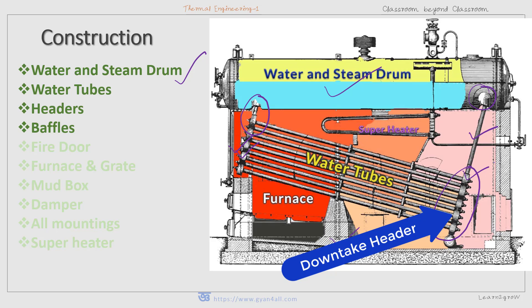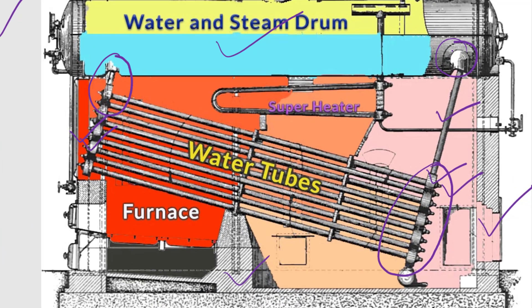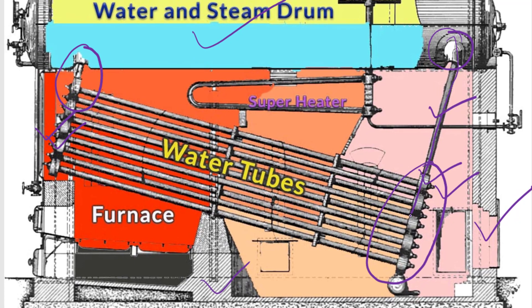The downtake header is placed at the chimney end of the boiler. This header joins the water tubes to the bottom of the drum. It collects water from the drum and flows it towards the other end through the water tubes. The water comes down through this downtake header and flows toward the water tubes.